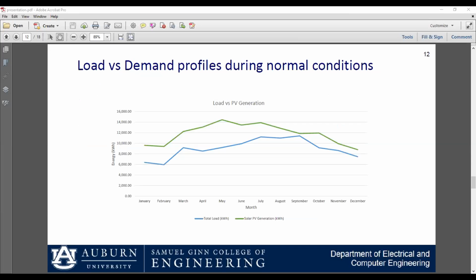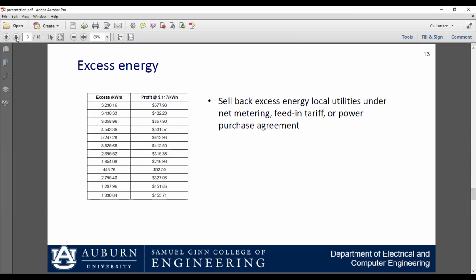So the PV system alone is able to meet the energy demands of the campus. We see the figure here, load versus PV generation, the monthly load in blue, and then the PV generation in green. Except for September, which had the highest monthly load, there was a bit of margin each month. This is the table of the excess energy each month. I realized I forgot the column here on the left for the month.